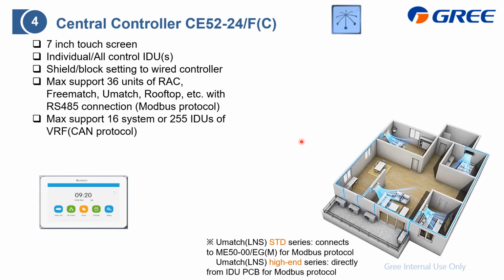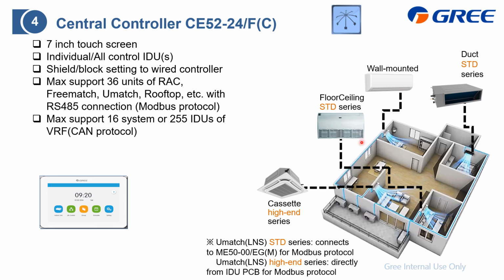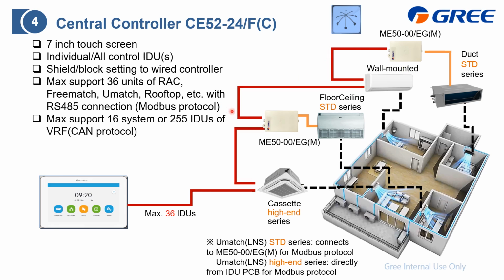And how to do the wiring to the UMatch? In this case, in this apartment, there are these 4 indoor units, or the 4 UMatch, with the standard and also the high-end model. And just like what I had introduced, for the standard, we need to apply this ME50 as an adapter to output the Modbus. And for the high-end or even the wall-mounted, it is automatically standard with the Modbus. So we can connect these in series, then connect to the central controller. Then with this one, we can control, in this case, these 4. Actually, at most we can support up to 36 indoor units.